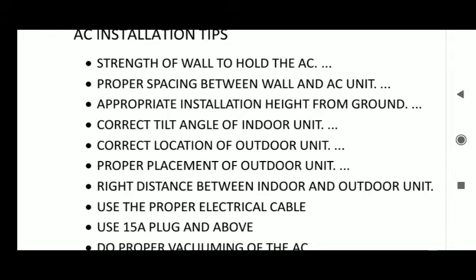Some people will drop them on the ground. Not that it is bad, but sometimes it sucks dust from the surface of the ground into itself, and this can affect or clog the condenser coil. Then correct tilt angle of indoor unit. You must tilt your indoor unit to a point where water will be flowing out.